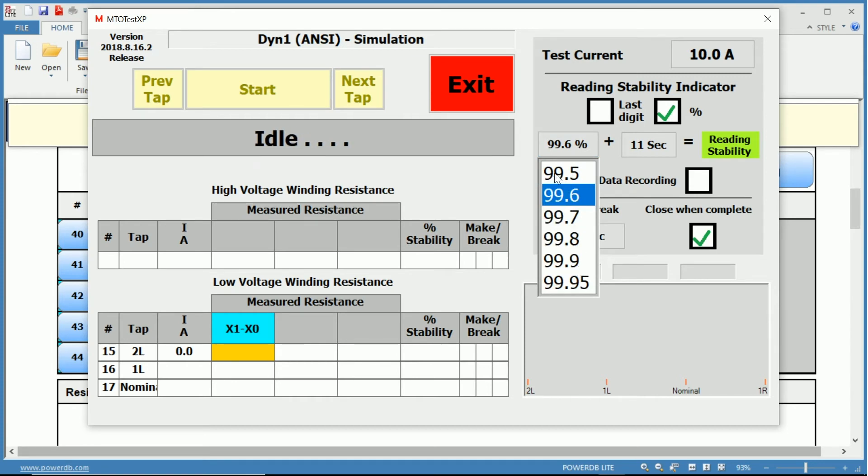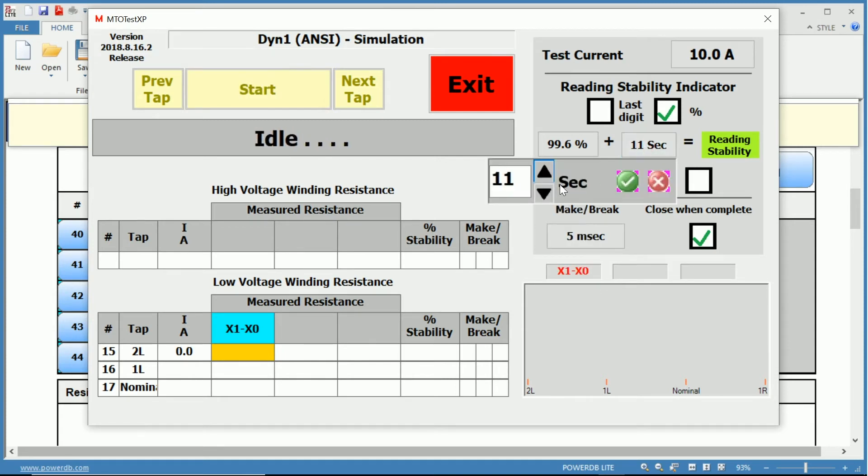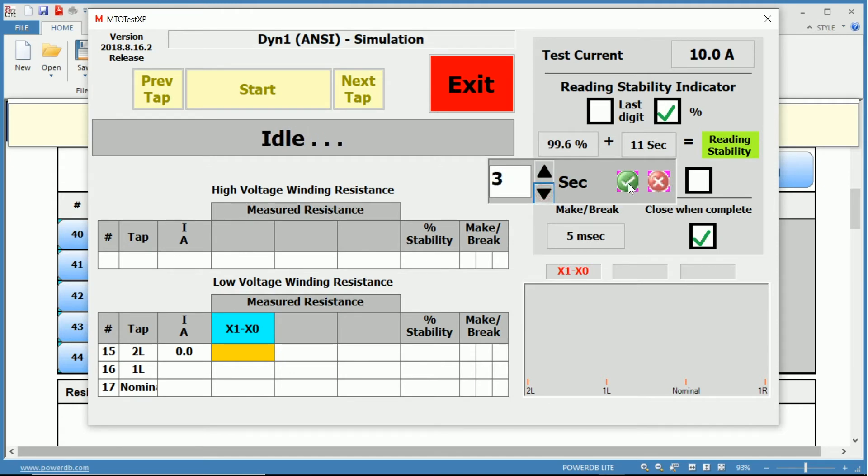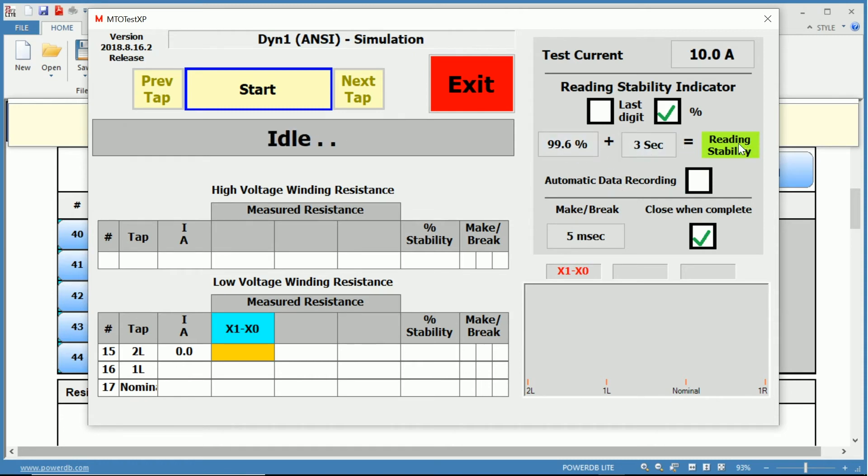Below that, we have our reading stability indicator, which can be in percentage, in which the current must be stable within this percentage, anywhere between 99.5 to 99.95 percent stable for the allotted time. For the purpose of this video, I'll lower this to three seconds.